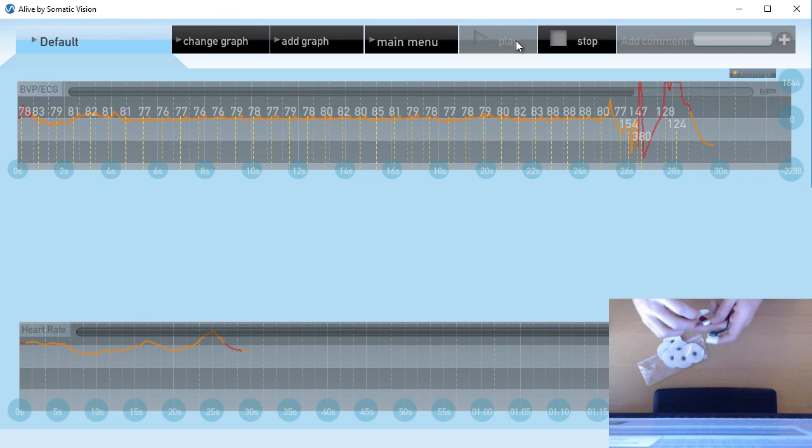Place the disposable electrodes instead of the permanent electrodes, making sure to keep the permanent electrode somewhere safe. You now need to peel the protective film from on top of the disposable electrode and place it somewhere with the white on the left side of your body, and the black on your right.